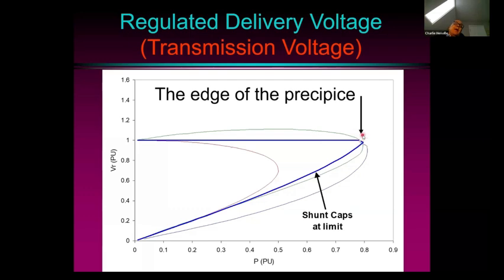So operators and planners would like to try and operate the power system as close as possible to the limit of capability without actually falling over the edge. And that's been the problem many times when some contingency or multiple contingencies arise. The system falls over the edge and you get a blackout.